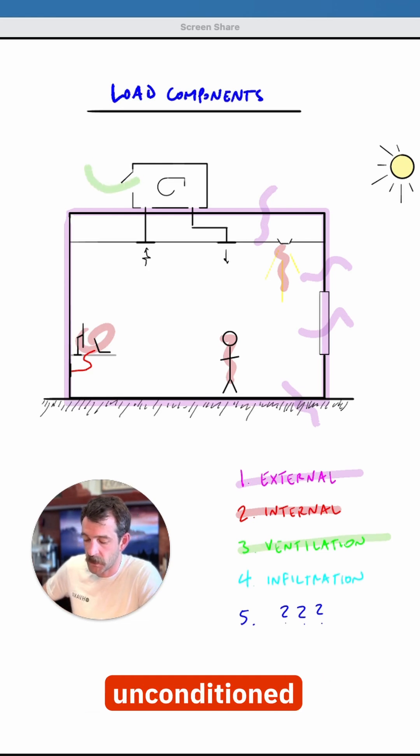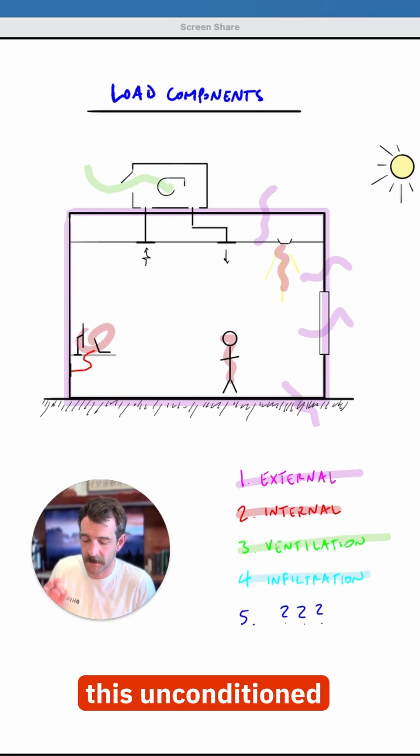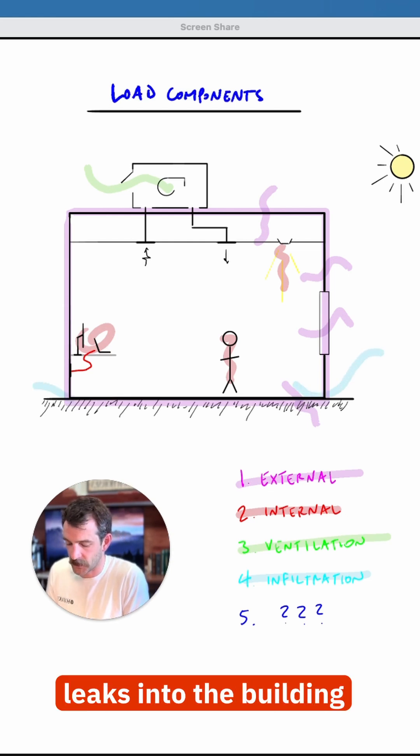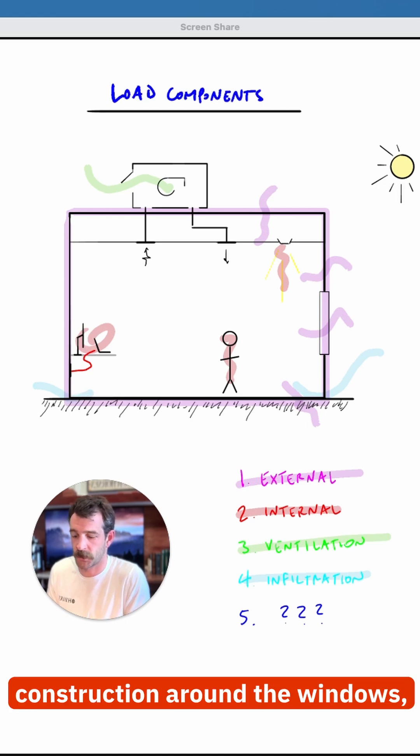Number three, ventilation. This is any heat added due to the introduction of unconditioned outside air into the system. This is done intentionally because people need fresh air. Number four, infiltration, is almost the same thing except this unconditioned outside air is not intentional. It's air that leaks into the building through cracks in the construction, around the windows, doors, anywhere that this air can leak in.